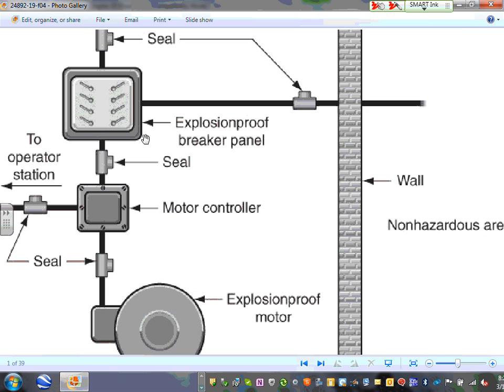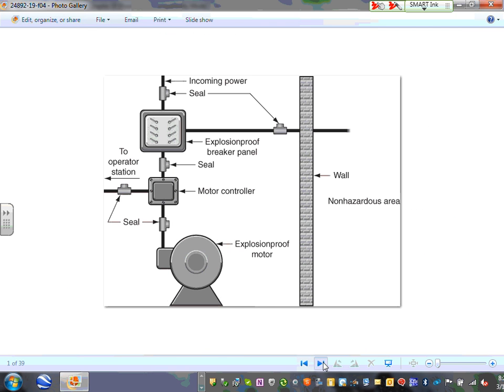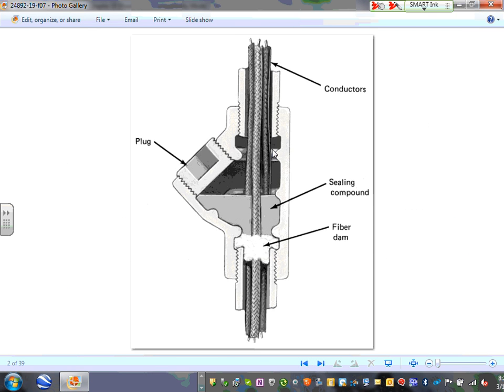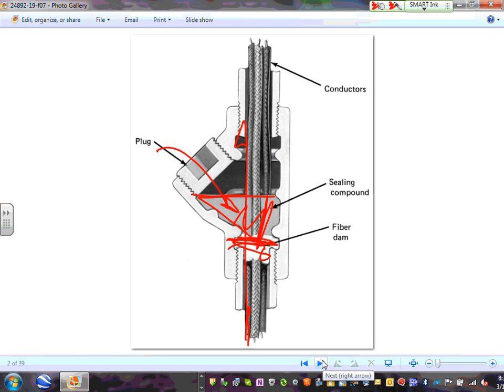We talked about, guys, the seal. Look at how big the explosion-proof is. I have a couple of pictures to show you. Here's how they do the seal, Adam. First, they do a fiber dam here. If you're an electrician, that's what you do. You put the fiber dam, and then you fill it with seal. You seal it, right? And the seal comes right in here. So the gas now cannot move through this at all. If you have a gas coming in here, it stops right here. Can't go anywhere. Now you minimize the explosions. That's your seal, vertical seal. And remember that you have to have a place for the water to drain.